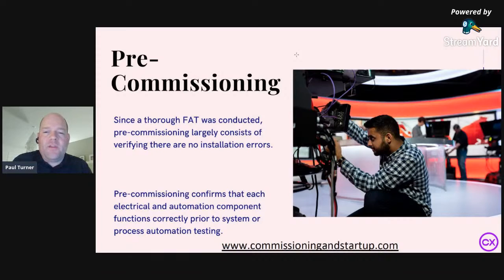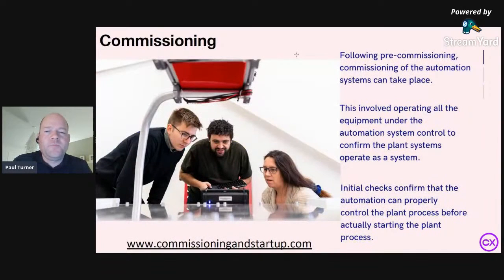You're getting the right response from the end device back to the PLC. All of the alarming and interlocking interfaces are verified during pre-commissioning, during loop checking, to ensure that all of the information you're getting on your HMI screens is correct and that you can access all the devices within the field. Once you can confirm that everything's interconnected correctly and all loop checks are completed, any additional electrical pre-commissioning is completed, such as high pot testing, or if you're working with large rotating machines, maybe short circuit or open circuit tests. Then we can move into the commissioning phase.